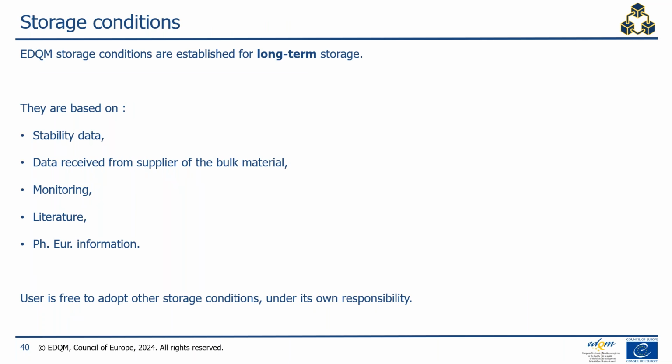The EDQM storage conditions are established for long-term storage. They are based on stability data, the data we have on the bulk material, some monitoring data, literature data, and any other information we may have. You may store reference standards differently in your lab, but you need to ensure that you can justify these conditions during inspections. It's your responsibility to demonstrate that.